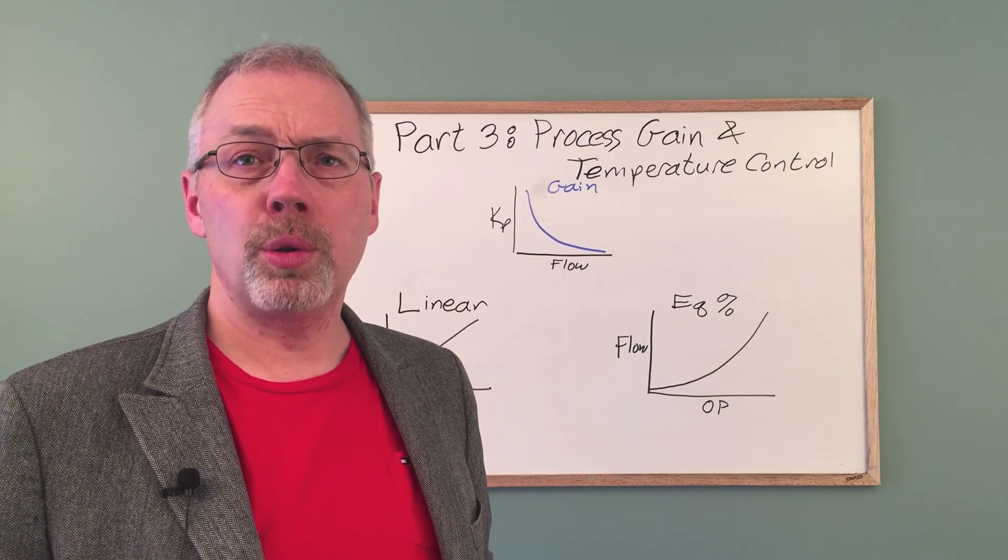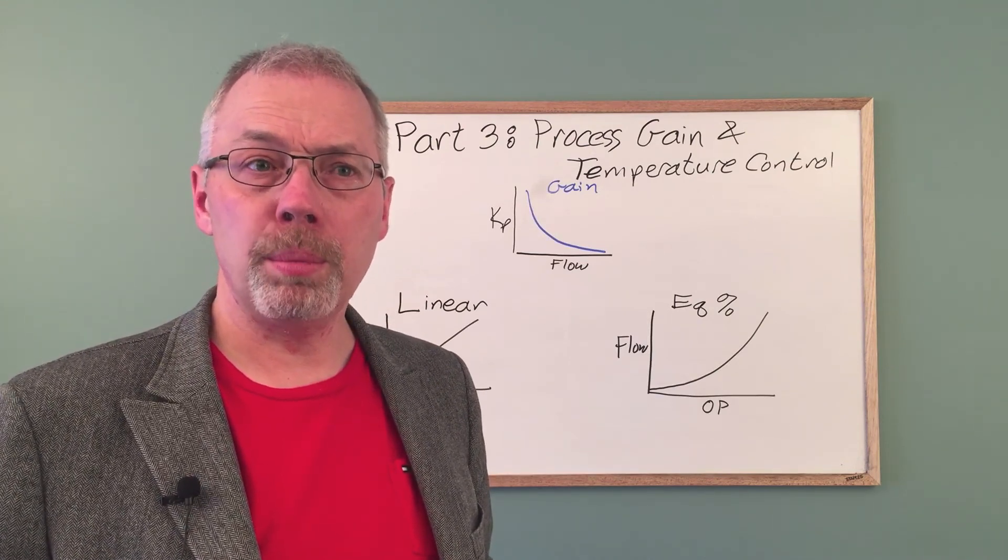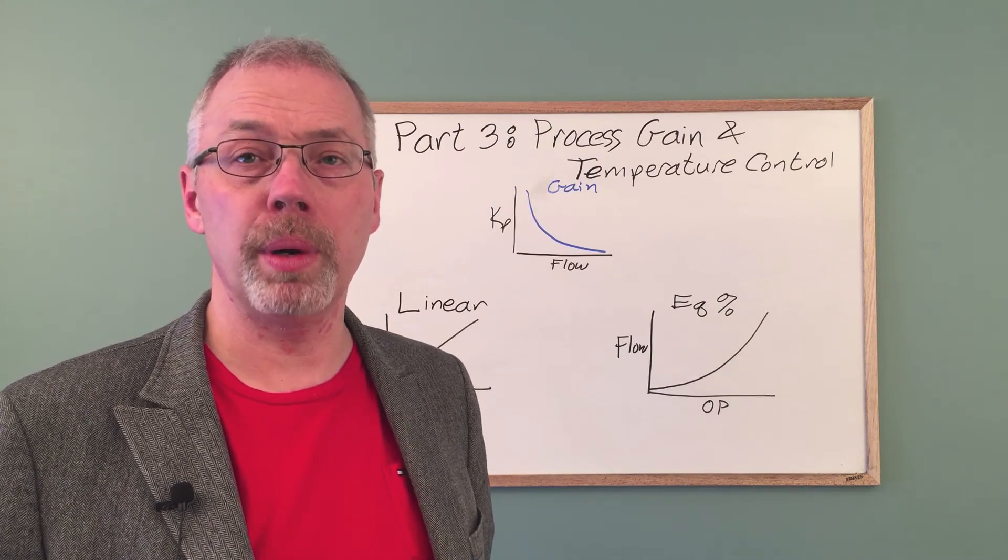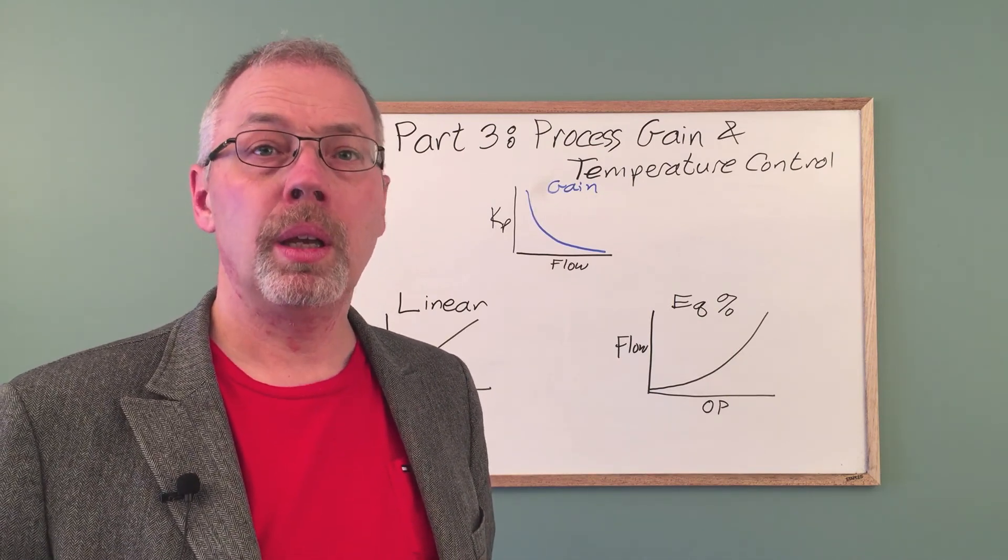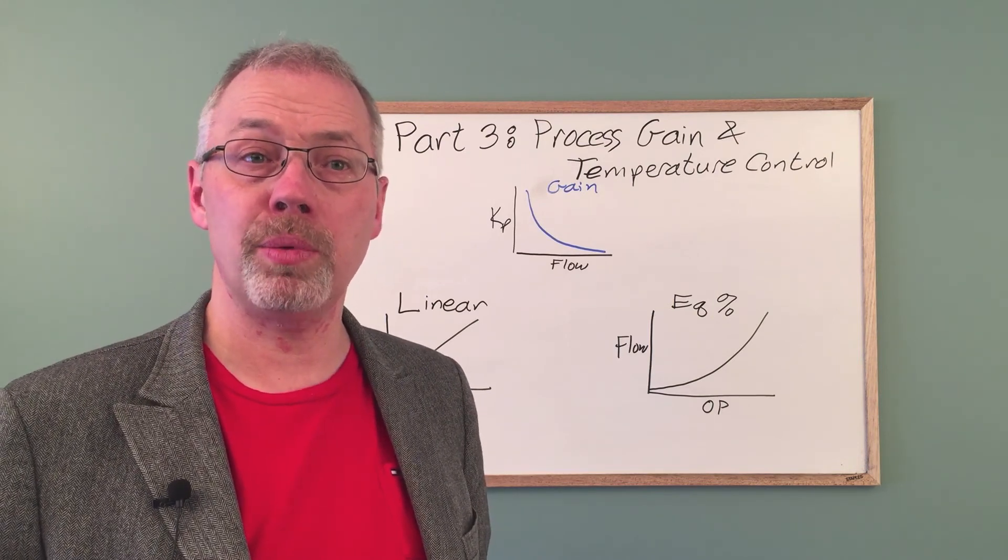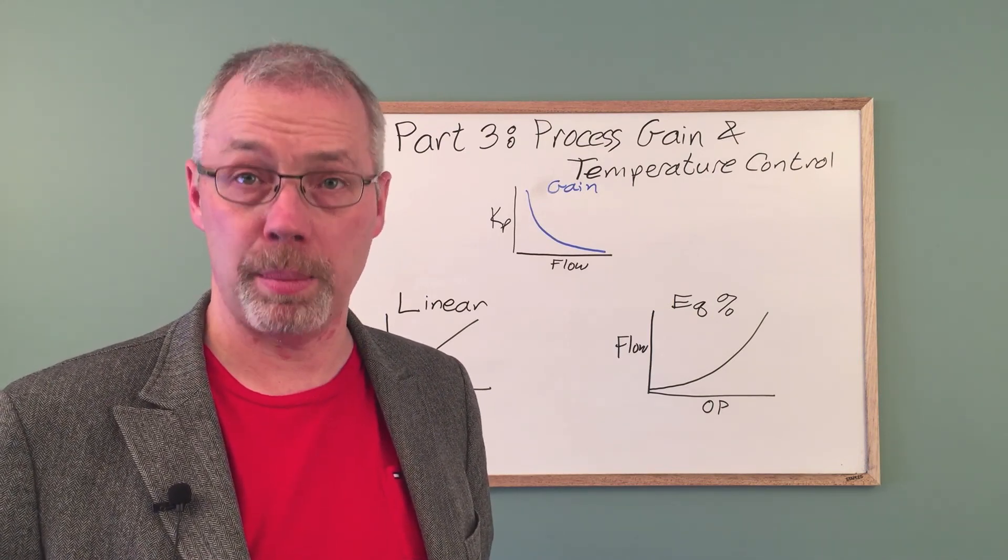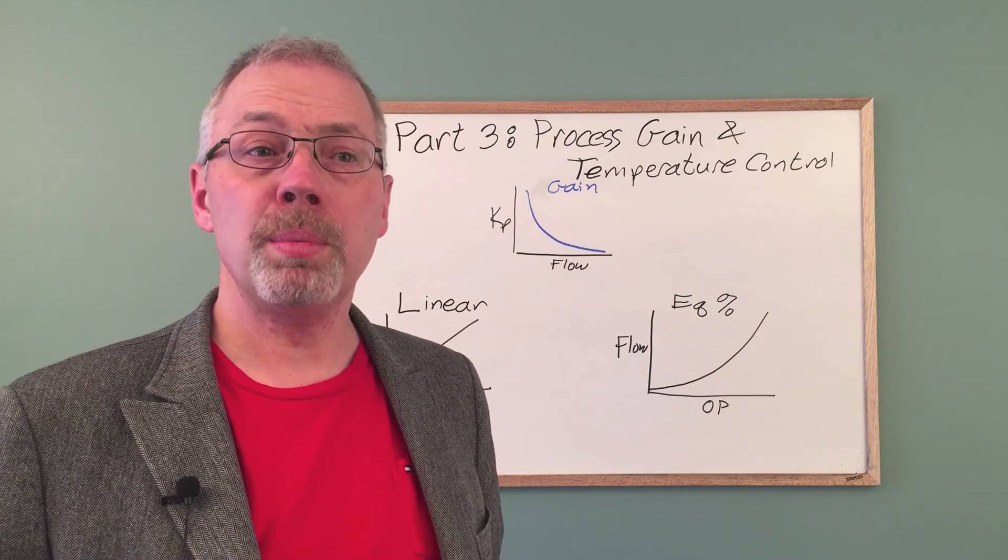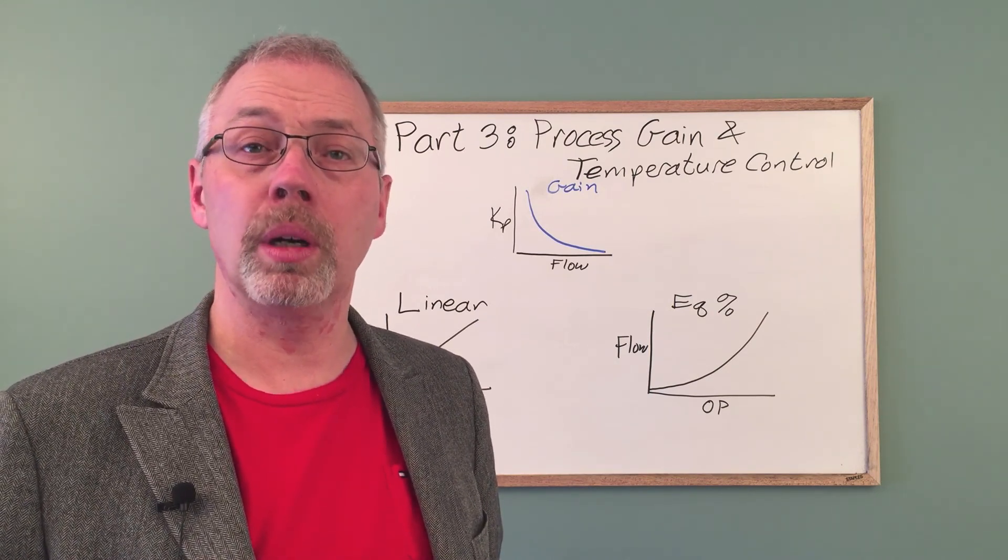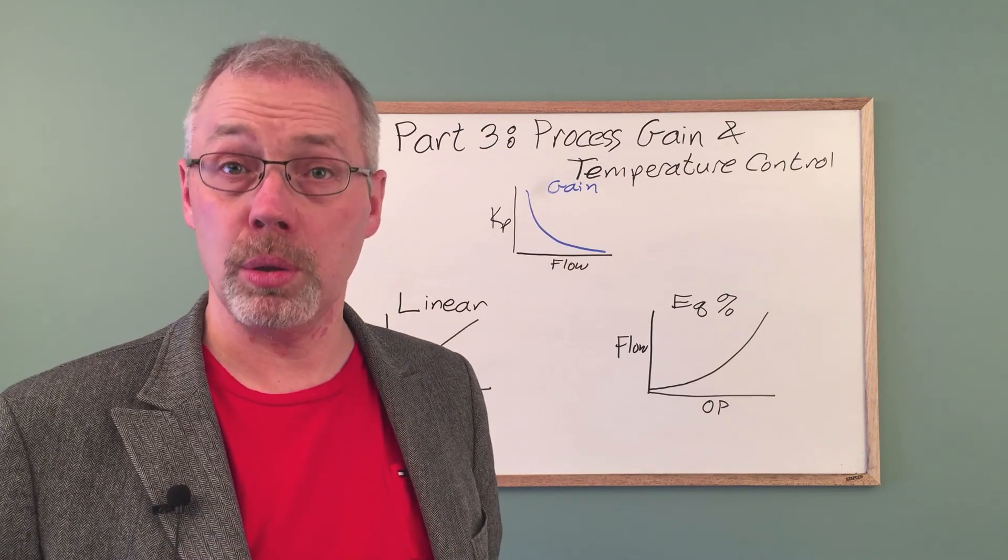We found that the choice of control valve characteristic is very important to ensure that the control system is robust over a wide range of operating conditions. An understanding of the hydraulic behavior will determine which type of trim is best suited for the application. This type of hydraulic modeling also allows us to tweak the control software where the wrong control valve is used.